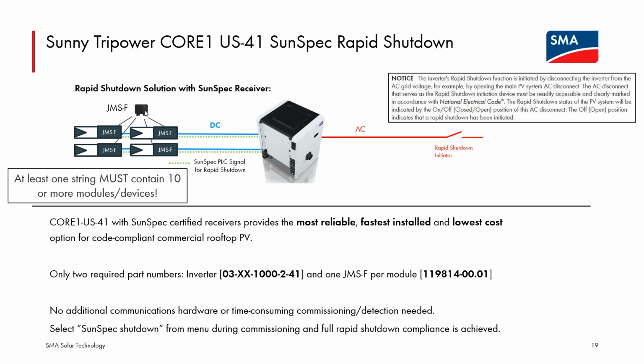If folks are very savvy with the specifications of SunSpec rapid shutdown, the standard says a minimum of 6 to a maximum of 30 devices per string, and I think you can have up to 10 strings paralleled and still, quote unquote, comply with their standard. We've gone a little further. We want to make sure that when the system's in shutdown, we'll have enough DC voltage from the array, even in shutdown, to ensure that the system will start back up correctly.